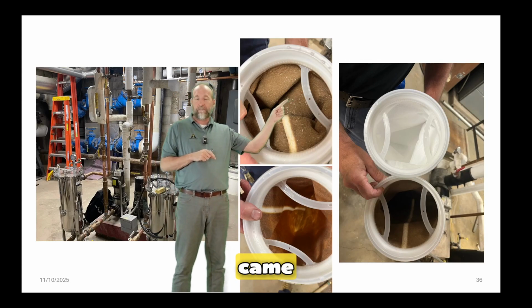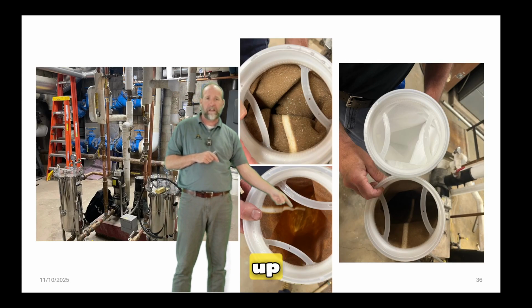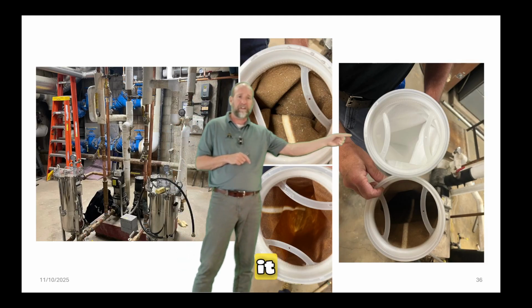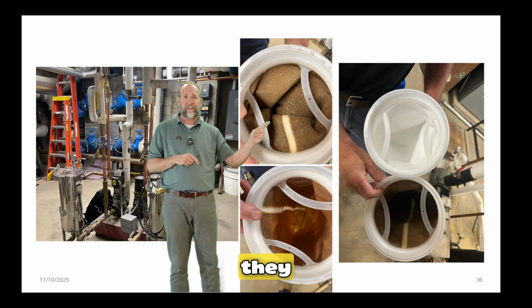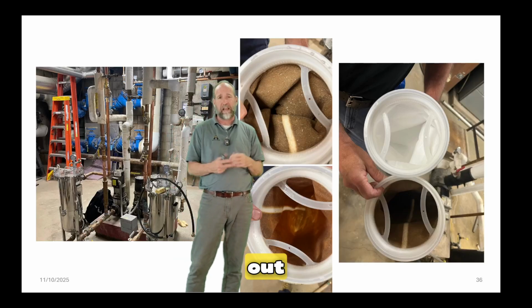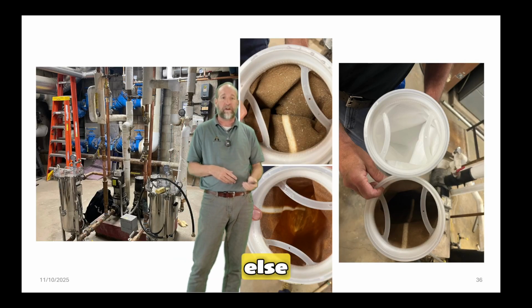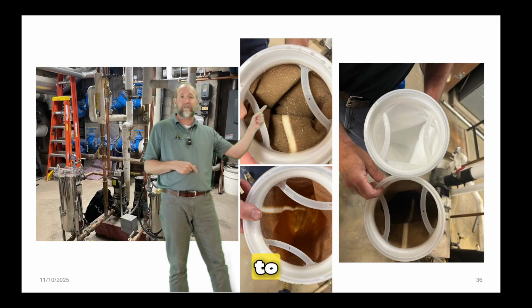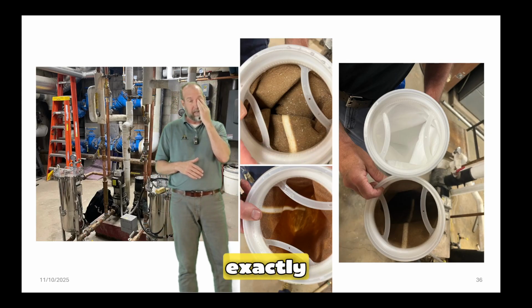And that scale that came off the inside of those pipes, this is where it ended up, was in these bags. And they were able to see it from clean all the way up until they see the scale. And you can turn those bags inside out and get the scale out of it and everything else. Again, this is the way to prove it out to a customer so they can see exactly what it is.